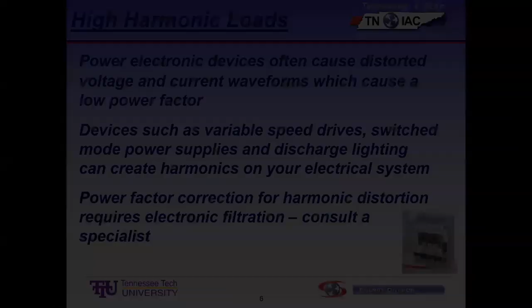In power electronic devices, if you monitor something like a computer power supply, they've got really chopped up waveforms. They're chopping this and doing that and the other, and they have power factors less than 1 as well. Usually for most industrial settings, the load from those devices is pretty small, but if you had a big data center, that would probably be the main source of a bad power factor.